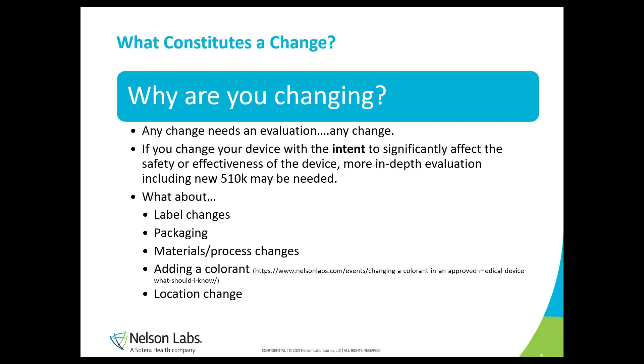If marketing, and by the way, I love hearing the discussions between engineers and marketing. I have a lot of friends in marketing, and I understand the point and the process, but sometimes adding something or changing a color because they want to add a color or change a color can cause a lot of issues to biocompatibility or even paperwork. So I always ask, do you have to do that? I know there's the internal discussion that needs to happen, but just remember, any of those changes, specifically adding coloring to a device, should have sufficient evaluation. And like we mentioned, location change. These are all things that we see could have an impact on biocompatibility.